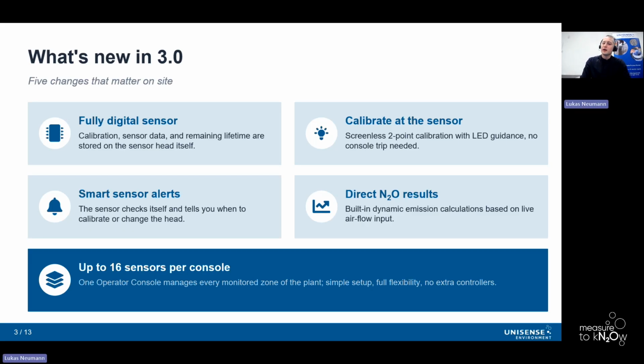So what's new specifically? We have the digital sensor, where everything about the sensor now lives on the sensor. You can move it to another tank. You can swap it between plants. You can replace the head. The history travels with the sensor body. Next, you can calibrate at the sensor, so you don't need to walk back to the console. There's an LED guidance on site, and it only takes a few minutes, which is a big time saver for the bigger plants. Next, we've integrated some smart sensor alerts. So the sensor, if you will, is self-aware, and it will tell you when it needs calibration or when the sensor head is nearing end of life before it affects the data quality.